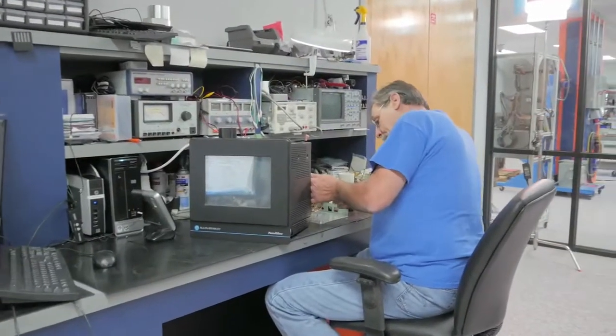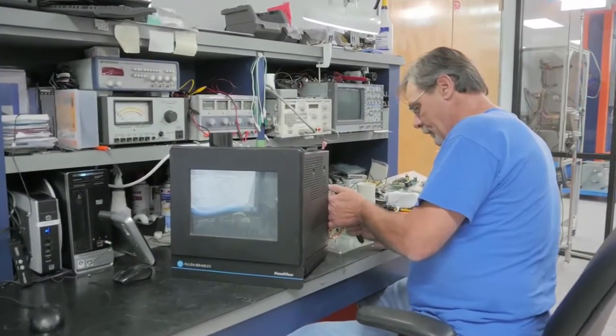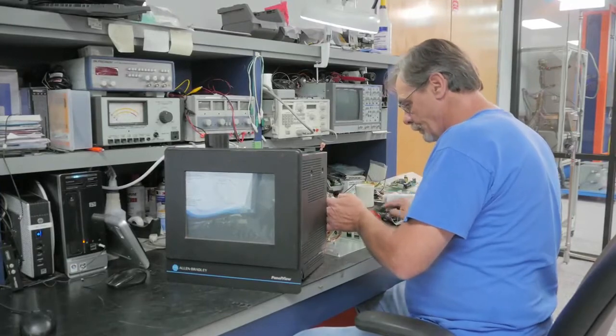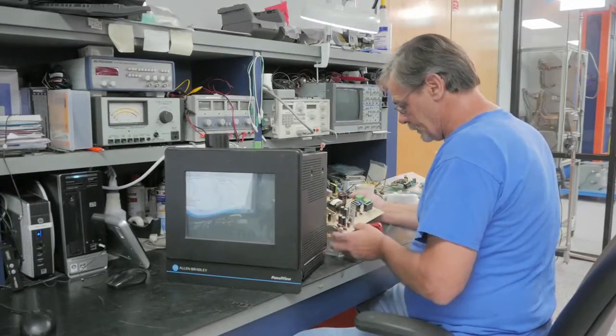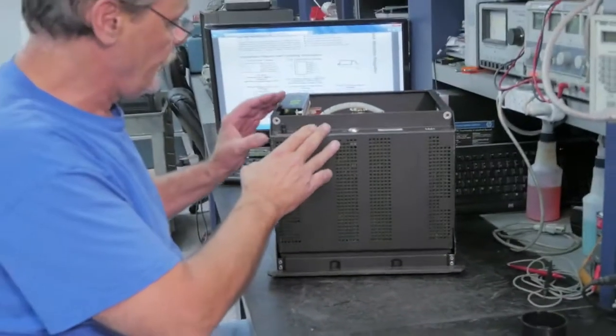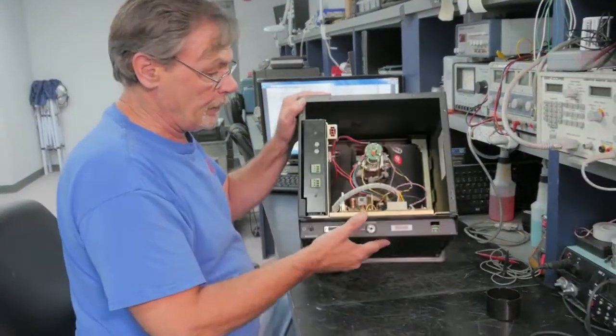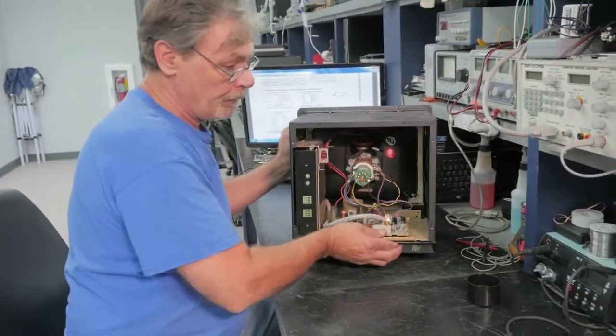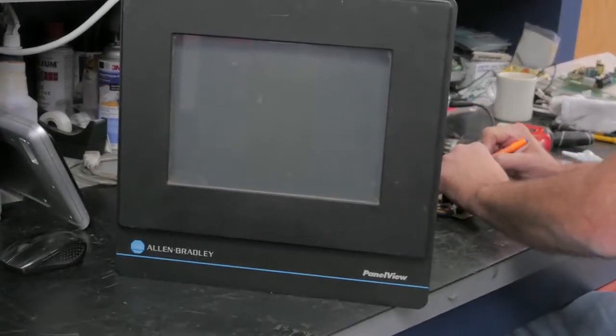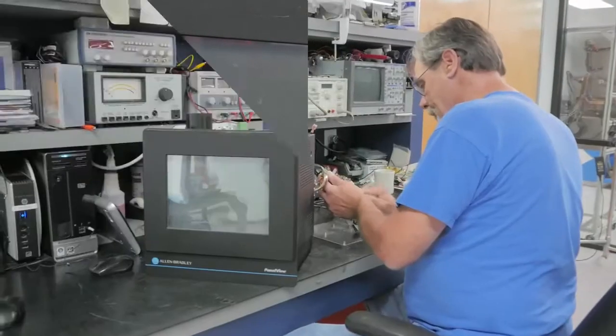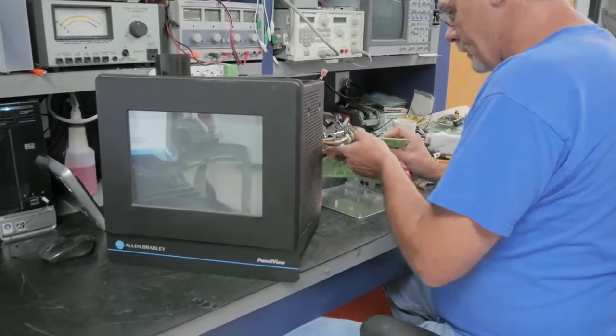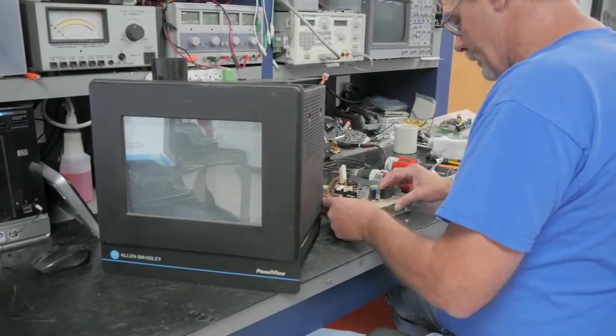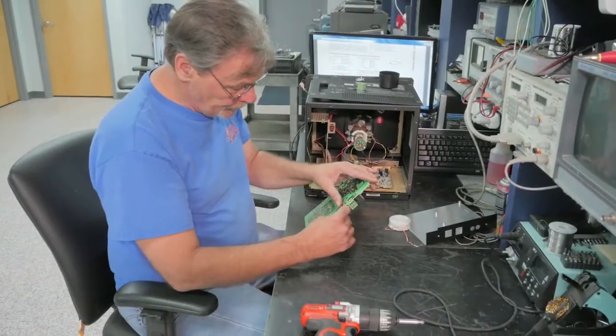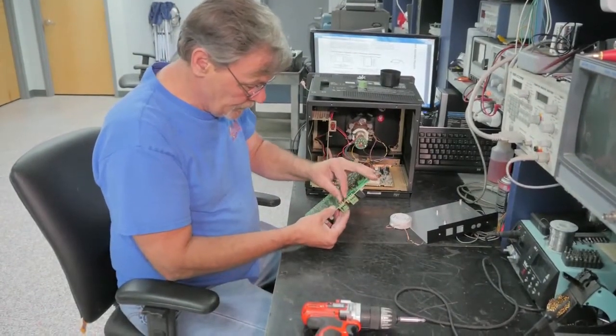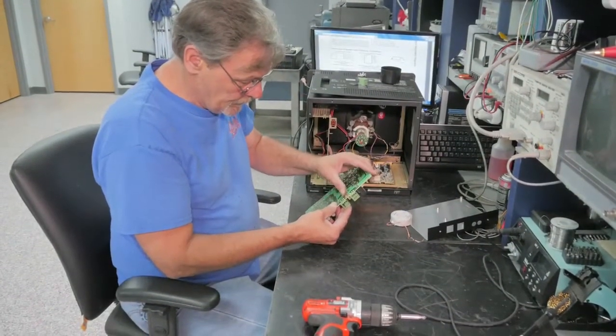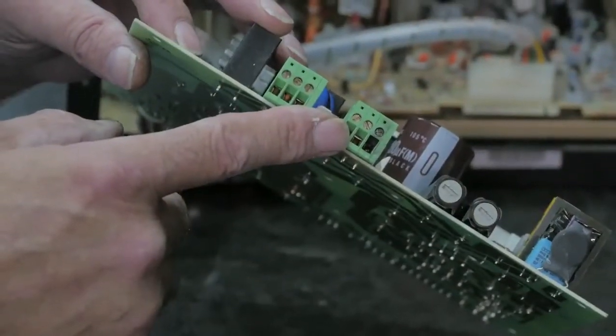At Global Electronic Services, we can component-level repair old and obsolete touchscreens, monitors, and workstations like this obsolete Allen-Bradley Panelview 1200. This Panelview came in with the AC power input burned. For this problem, the technician has removed the power board and tested each of the components. Component testing revealed a shorted AC line, bad bridge rectifier, and as you can see, the input connector is burned.